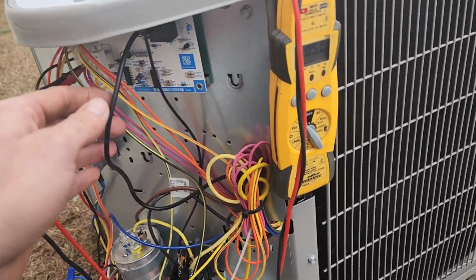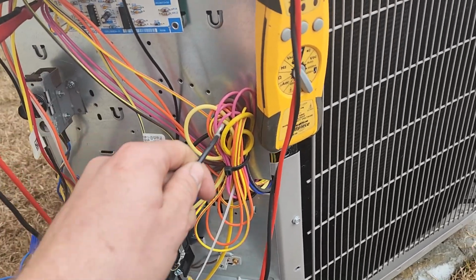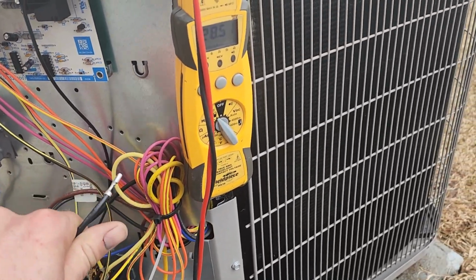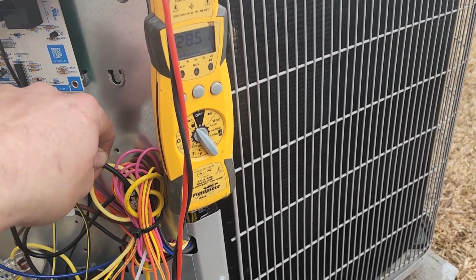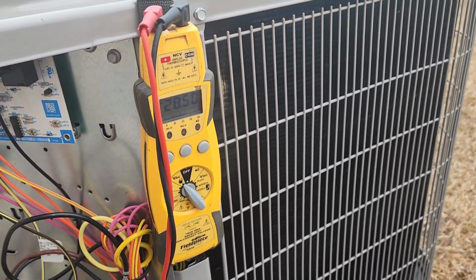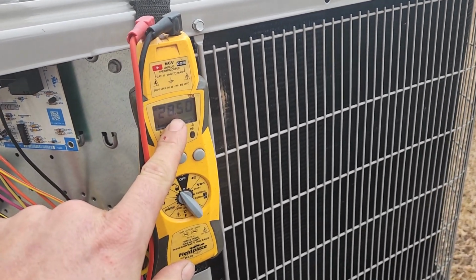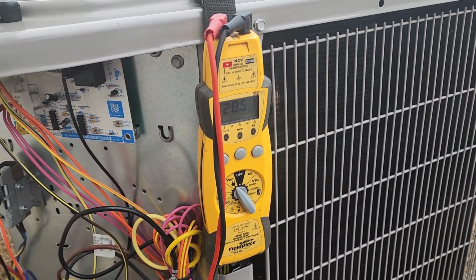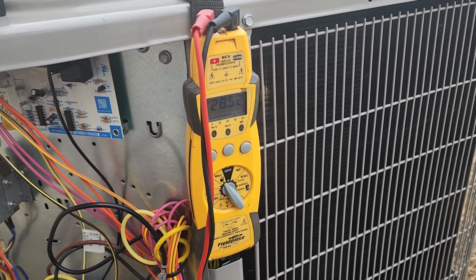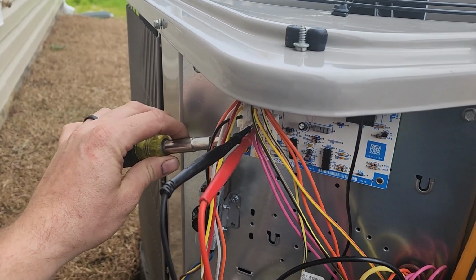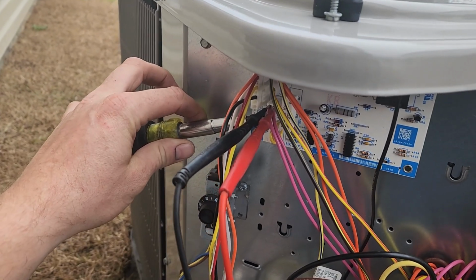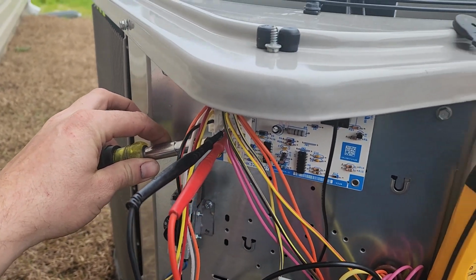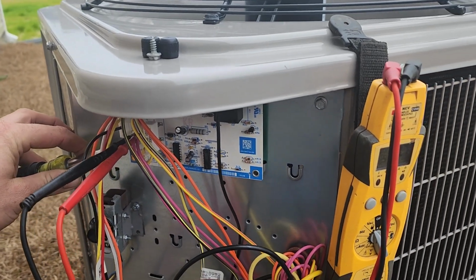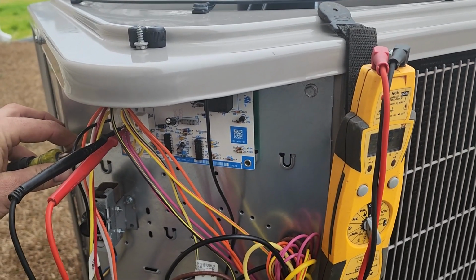Let's pull this fan. We're gonna let this run without the fan until this sensor closes and test our defrost. This is what I wanted you guys to hear, because I can almost guarantee the screeching is this defrost cycle. So we got our pins jumped, should be shifting here in just a couple seconds.